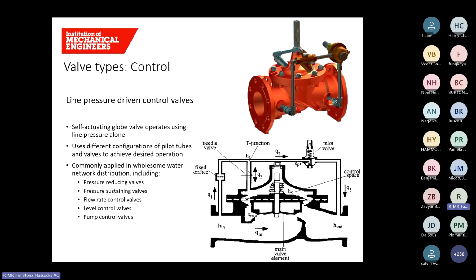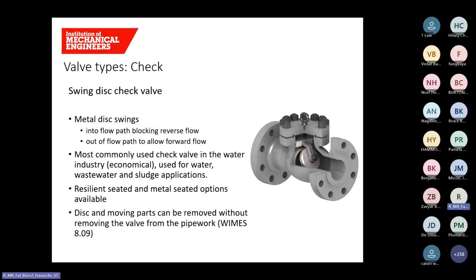The valve achieves the desired operation through various pilot tube and valve arrangements. These are commonly used in water network distribution, and the control functions are shown there. So you've got pressure reducing, pressure sustaining, flow rate control, level and pump control. Now on to check valves, or non-return valves. This is the swing disc check valve, and it consists of a metal disc which swings into the flow path, blocking reverse flow, or out of the flow path to allow flow to pass forward.